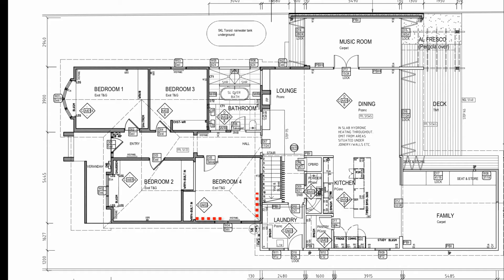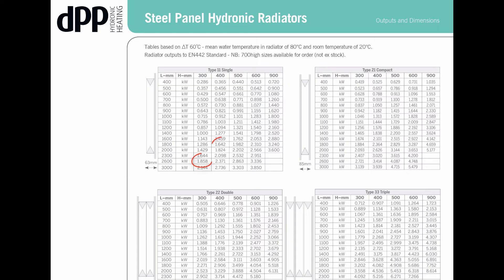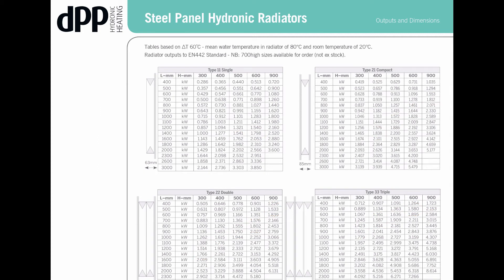From the dimensions of the room, in this example we've calculated the bedroom floor needs 1.656 kilowatts. With a known kilowatt requirement we can now consult our sizing diagram. As you can see there is a very large range of sizes that will suit that kilowatt rating.